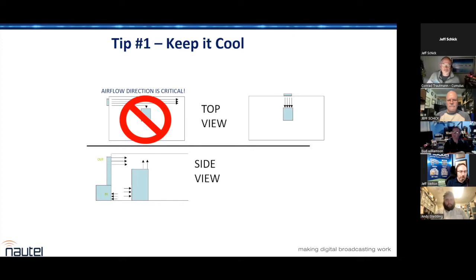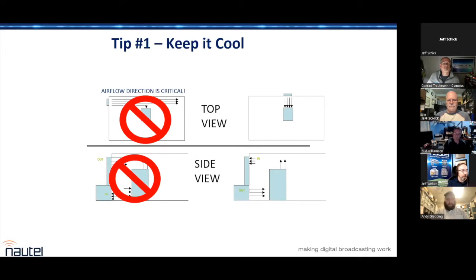In a transmitter facility, the air intake is usually at the rear and the hot air exhaust is almost always out the top, so those air conditioners are built 100% upside down. You really need to do some creative ducting to reverse the airflow direction so you're not pulling cool air away from the transmitter intakes and mixing it with the transmitter exhaust up top. You'll get a lot more efficiency and better life out of both your transmitter and your air conditioner if you spend $1,000 on sheet metal work. I've seen a lot of sites like that where doing a little sheet metal work made all the difference in the world.